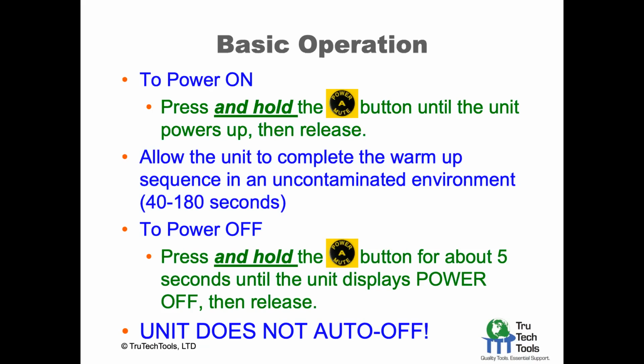The unit does not auto power off. It's in that kind of regime of safety products where you don't want it to stop working for you, because you can actually leave it on if you're doing work. If there's any chance you think the concentration of combustible gases might change, I mean, you're just talking about batteries, leave the unit on. It's going to scream when it goes above 10% LEL.